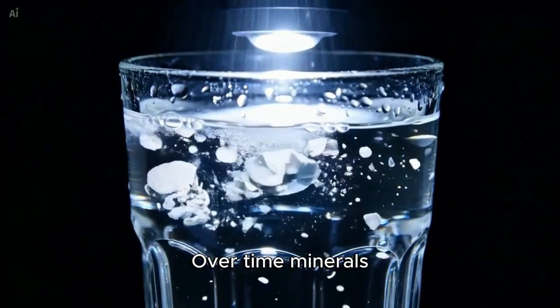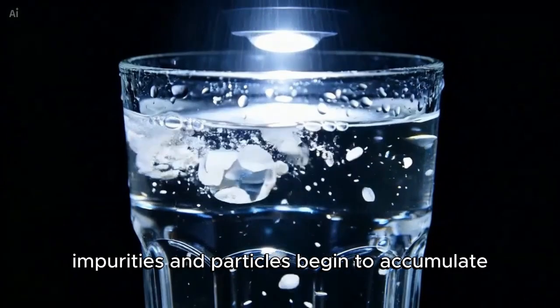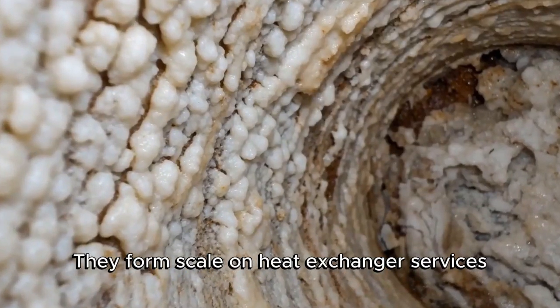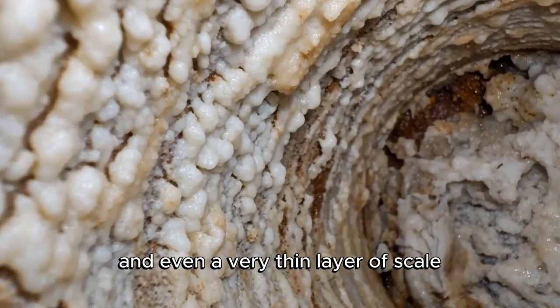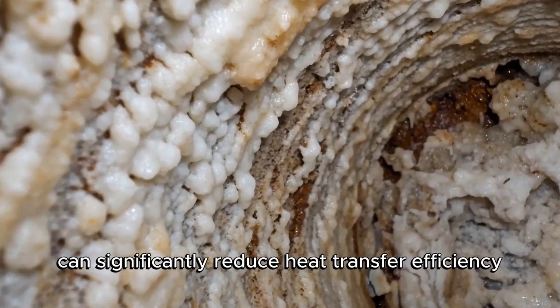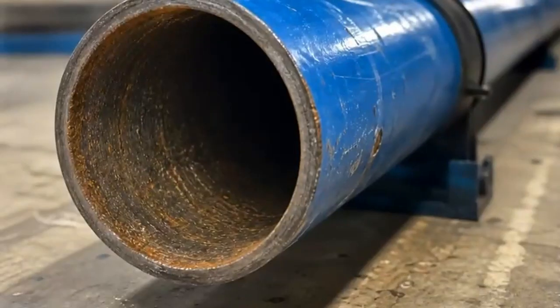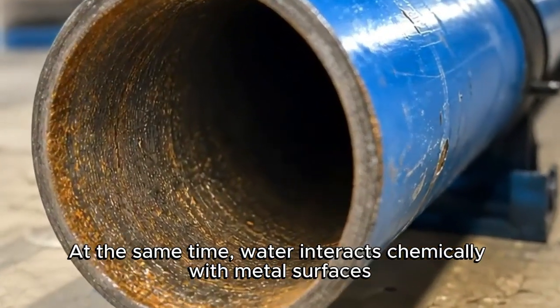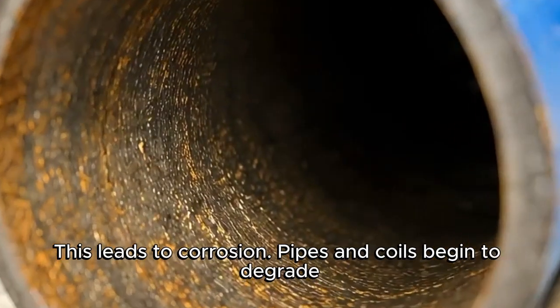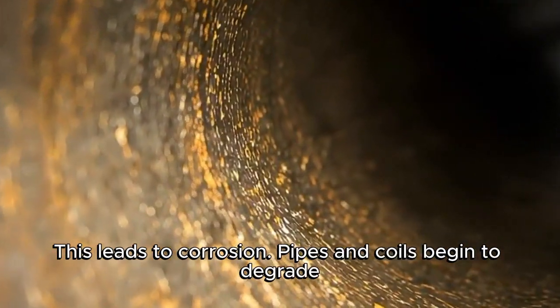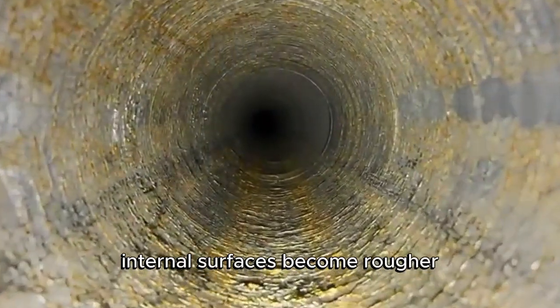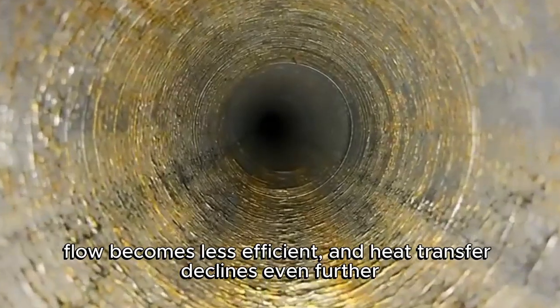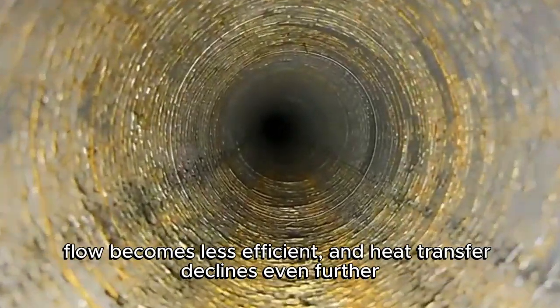Over time, minerals, impurities, and particles begin to accumulate. They form scale on heat exchanger surfaces, and even a very thin layer of scale can significantly reduce heat transfer efficiency. At the same time, water interacts chemically with metal surfaces. This leads to corrosion. Pipes and coils begin to degrade. Internal surfaces become rougher. Flow becomes less efficient, and heat transfer declines even further.